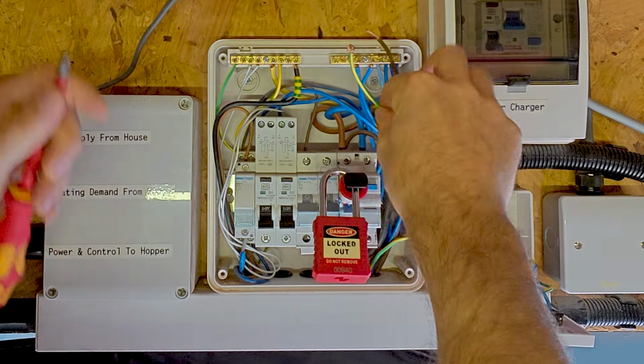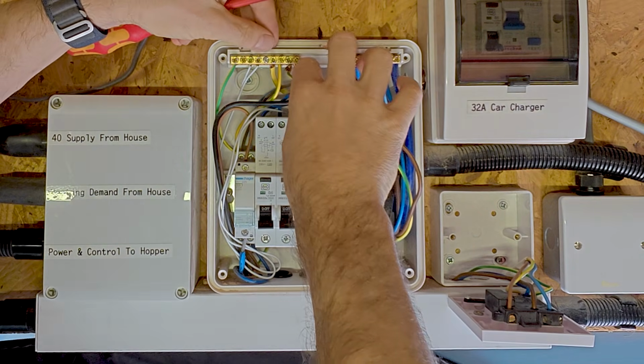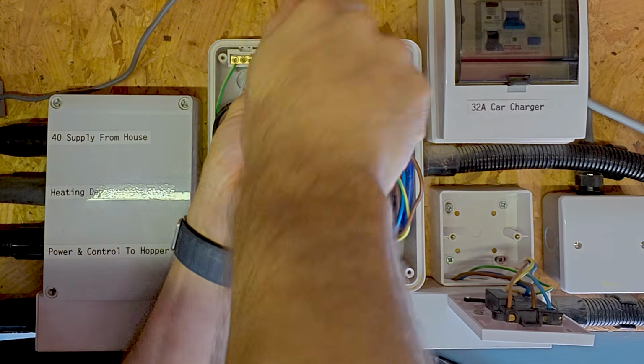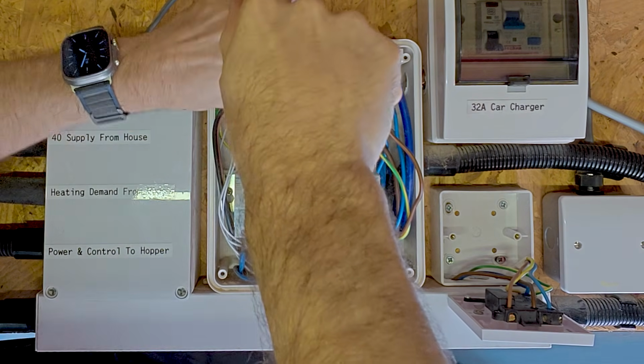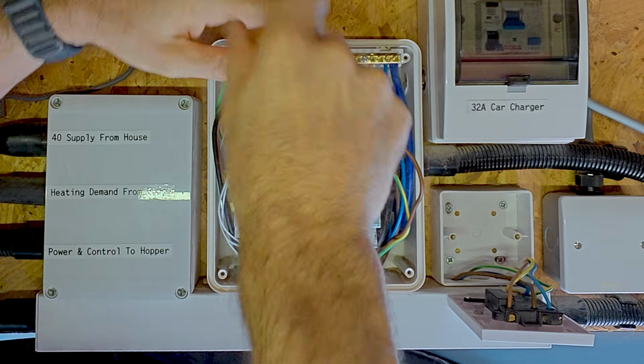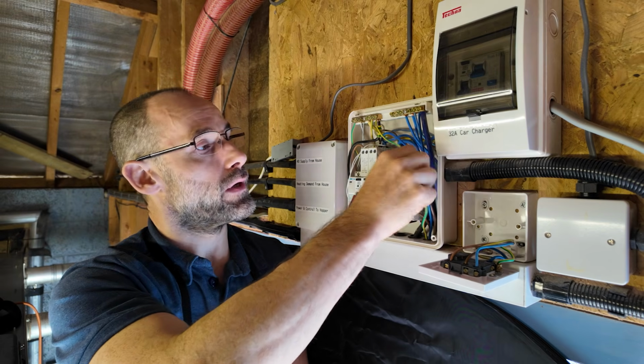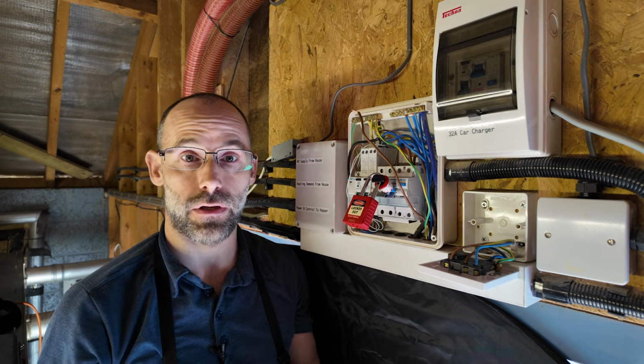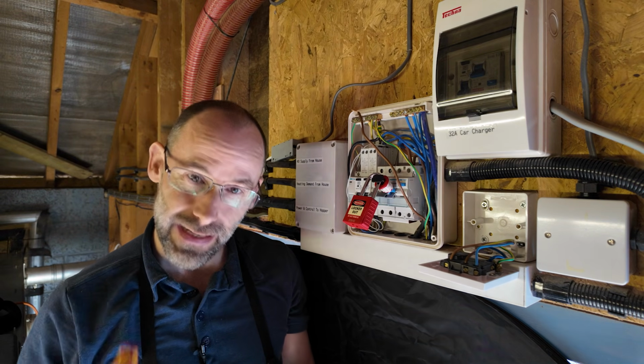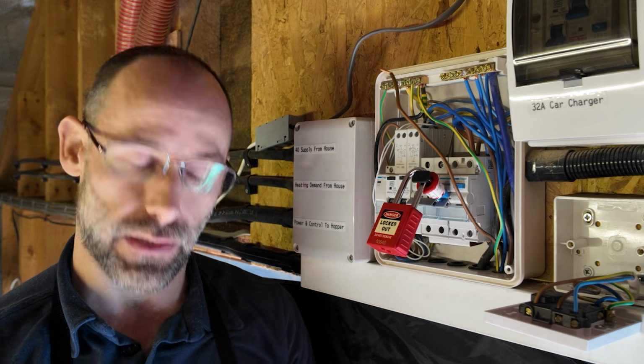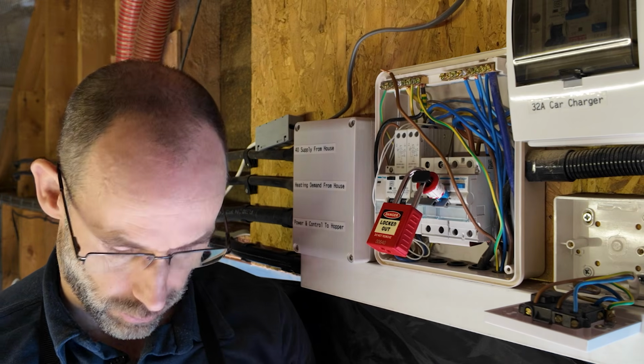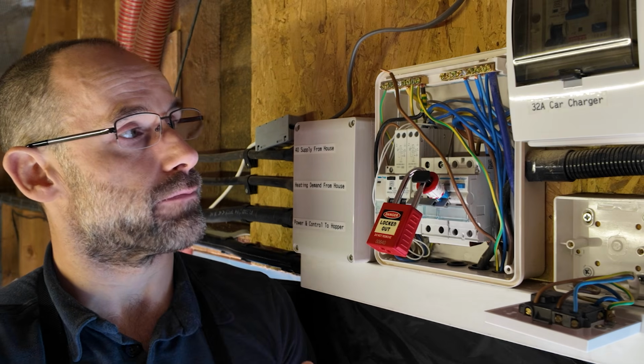All right, so first thing I'm going to do before we do an insulation resistance test is get this CPC back in the bar here, because remember, I said this test is going to be putting a test voltage, in this case 500 volts DC, into the wires, and we want to make sure that we don't have anything anywhere in the installation with 500 volts on it, even though it's only a little tiny energy pulse that realistically won't hurt anybody. It just gives you like a static shock. This is still the best practice.